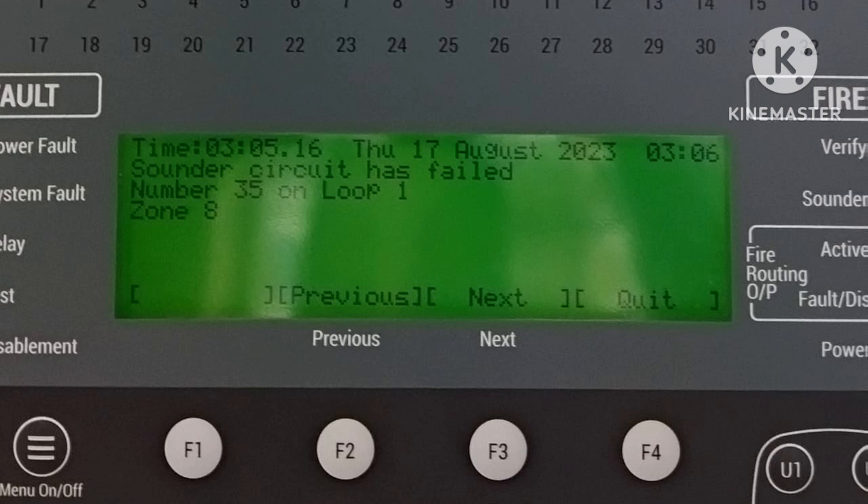Sounder circuit has failed means the hardware of the sounder is not working properly. Check or reset it; if it does not resolve, replace the sounder. This is the sounder problem — specifically the loop-powered sounder has a problem and needs to be checked.